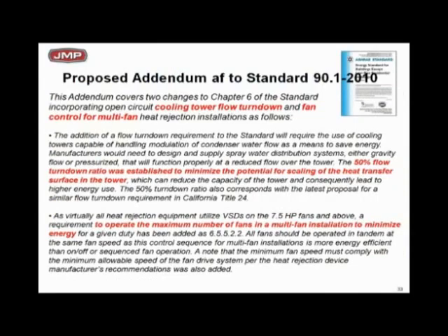Regarding ASHRAE 90.1 2010: an addendum was issued, passed, and approved — it is part of both ASHRAE 90.1 2010 and 90.1 2013. It states in red that a 50% flow turn down ratio is the minimum. So if you specify that your towers be ASHRAE 90.1 2010 compliant, you will get 50% turn down. I would suggest including that in your guide specifications — it's a simple but important requirement.